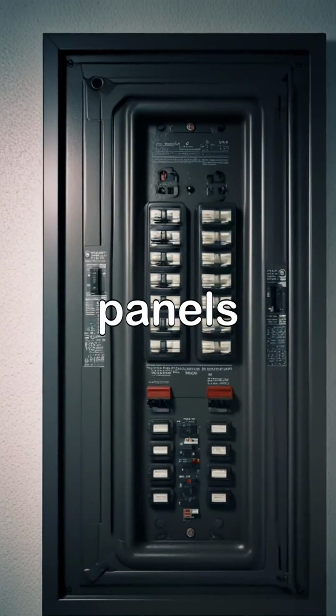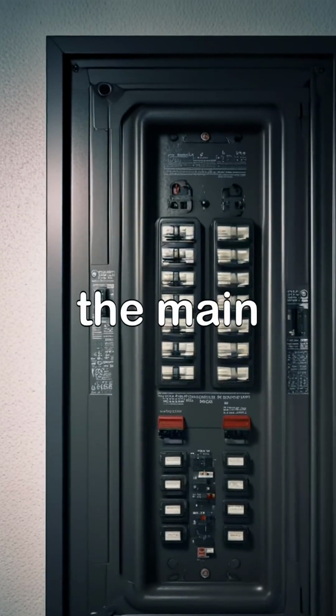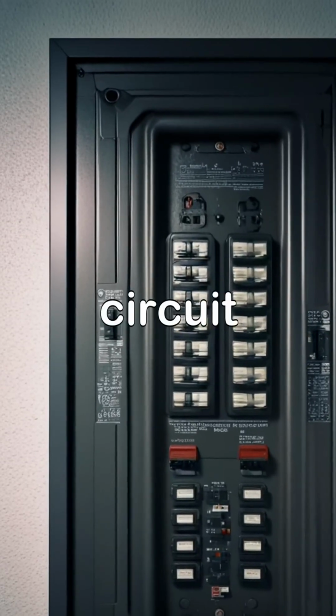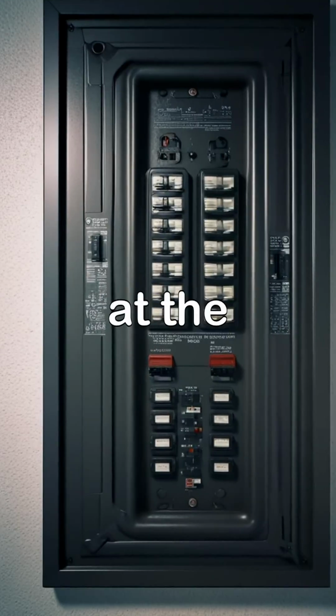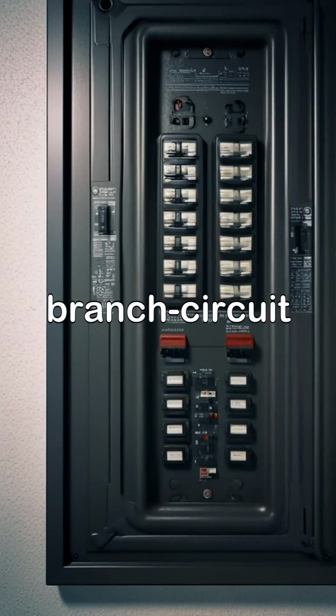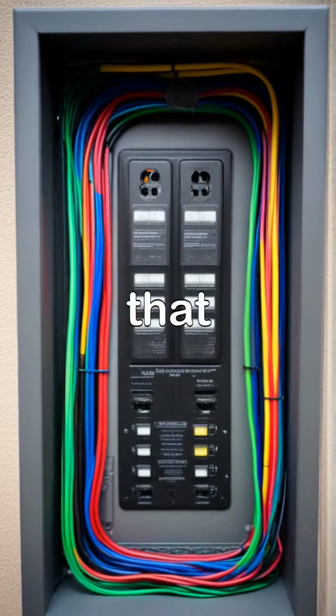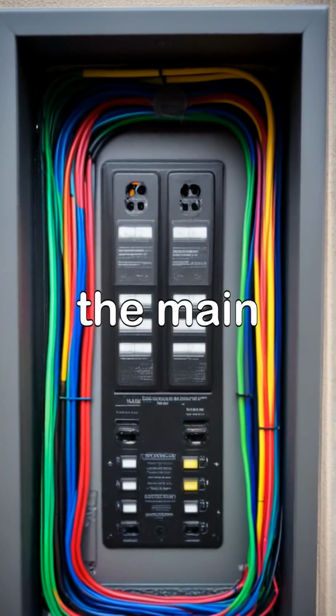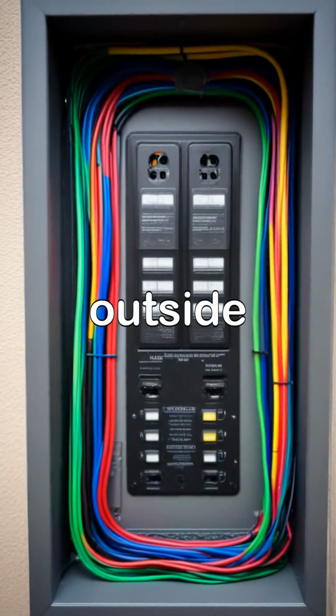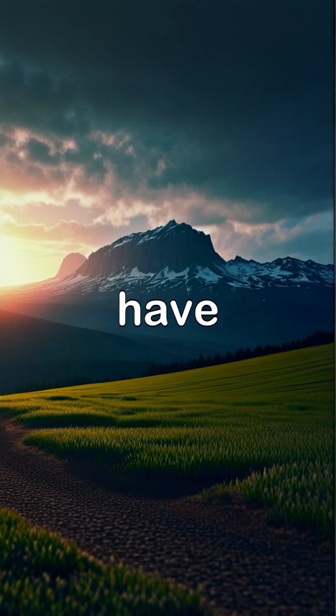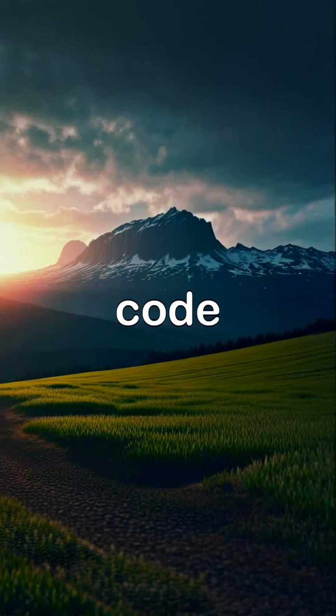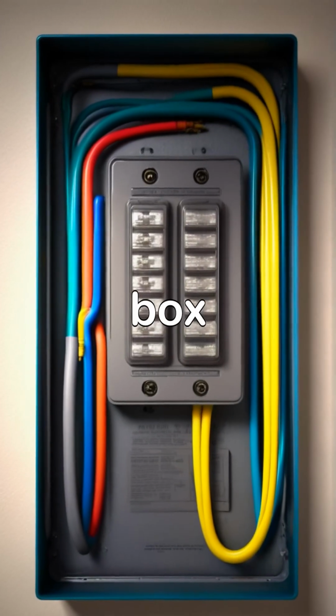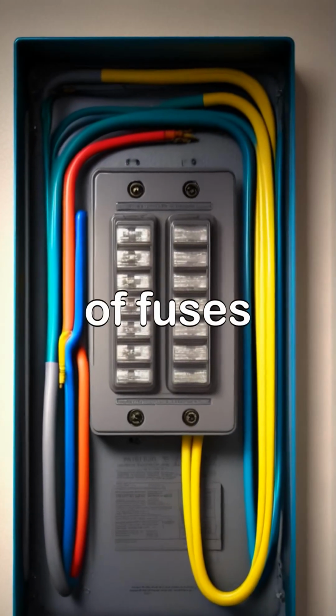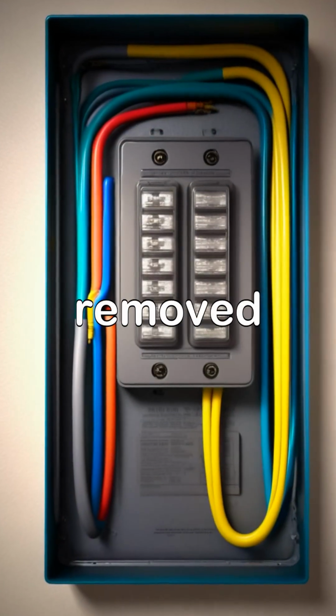Most contemporary panels combine the main disconnect and the main overcurrent protection device in the main circuit breaker, usually located at the top of the panel just above the branch circuit breakers. However, you should be aware that some local electrical codes require the main disconnect to be located outside, away from the service panel. You will have to use the type required by your community's code. If your home has a fuse box, the main disconnect will consist of a pair of fuses mounted in a pullout, which is removed to cut the power.